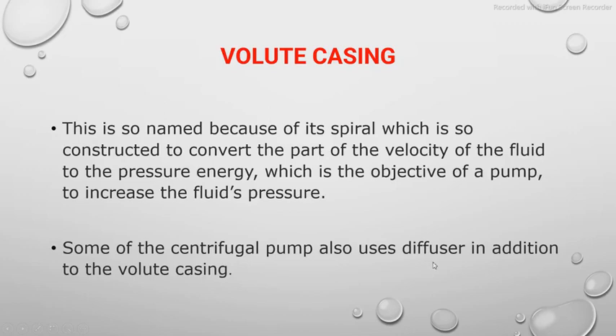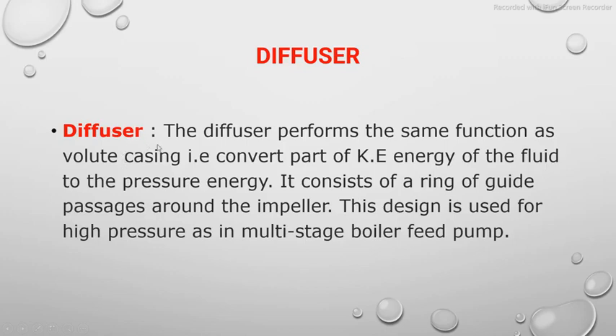Some centrifugal pumps also use a diffuser in addition to the volute casing in order to achieve much higher pressure. The diffuser performs the same function as the volute casing — converting the kinetic energy of the fluid to pressure energy. Construction-wise, it consists of a ring of guide vanes that reduce the velocity of the fluid, causing an increase in pressure energy.